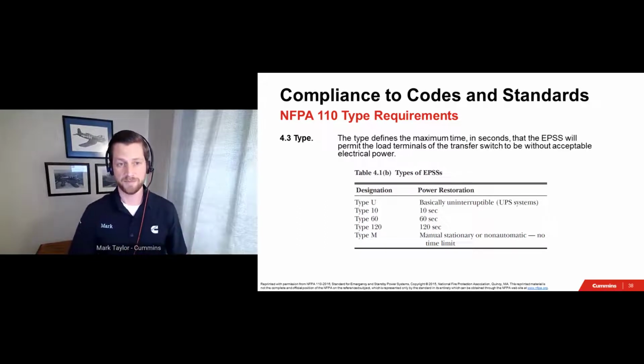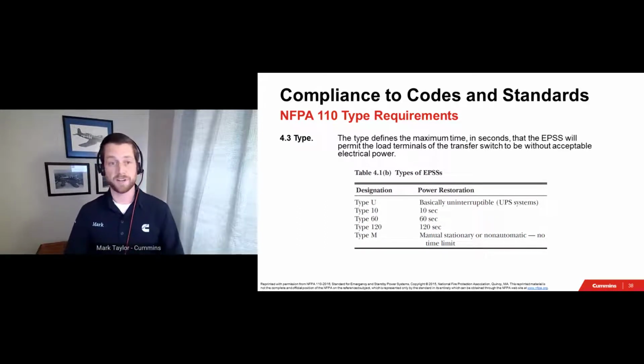Types can come in a variety of designations, but for life safety applications, you will most likely see requirements for type 10, for 10 seconds, and you may also have encountered requirements for 60 or 120 seconds for other types of loads. What you will not see here, however, is NFPA 110 calling out a fuel type for emergency power source in order to fit the requirements of one type or the other.